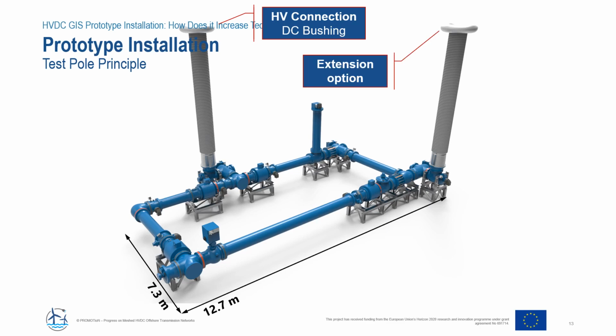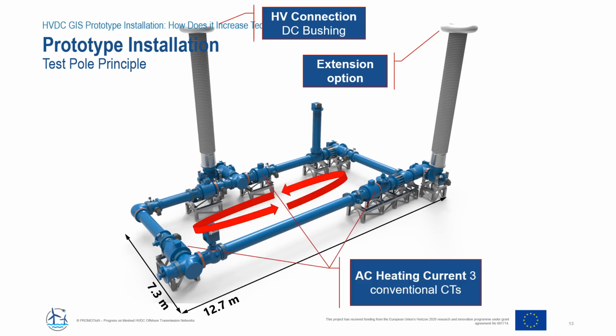We have a second bushing to do some extended tests where we test the voltage withstand of an open disconnector gap. And the test pole has the form of a ring to be able to induce a heating current using conventional current transformers, so that we can also have thermal stress and the influence of the high temperatures on the dielectrics as part of the test.